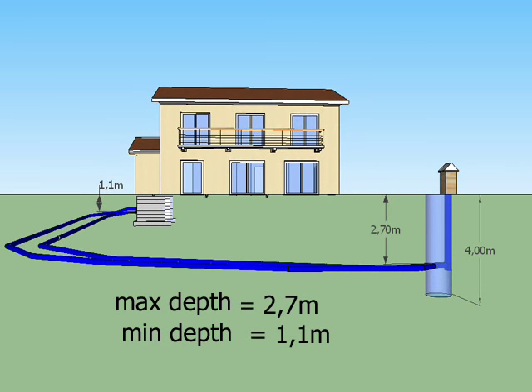The air entrance in this case is located at the lowest point at minus 2.7 meters and slightly ramped up to minus 1.1 meters close to the house.